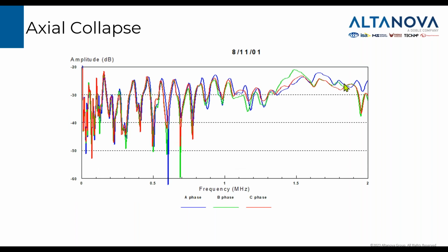These are 3 phases measured across, I think it was the common winding. In this case, it is presented in linear scale. You can see the bottom scale is no longer logarithmic, it's linear. So we don't see very well what's happening in lower frequencies, but we see much better what is happening in the highest frequency range. If we use logarithmic scale, all the features visible here will be just in the corner somewhere. So this scale was apparently the good choice. What we saw here was a little difference between the blue line, representing A phase, and the other 2 phases. If you look carefully, it stands out from the other 2 phases more than they do from each other. Is it enough to tell something is bad with these results?